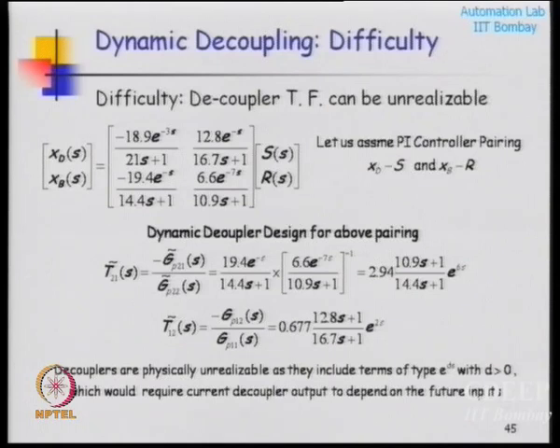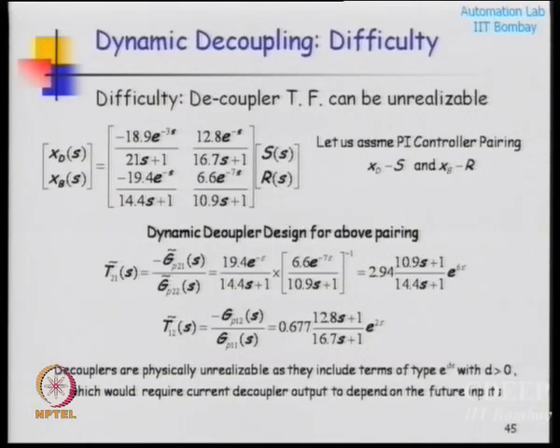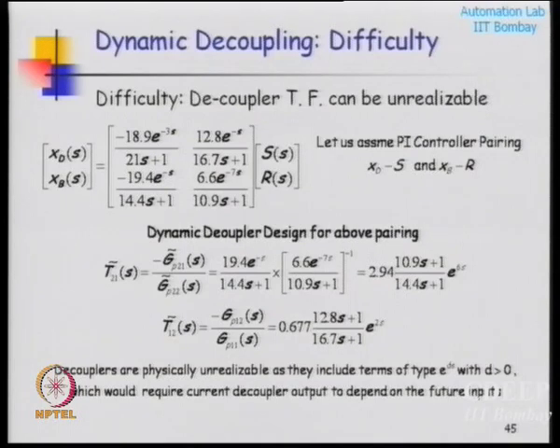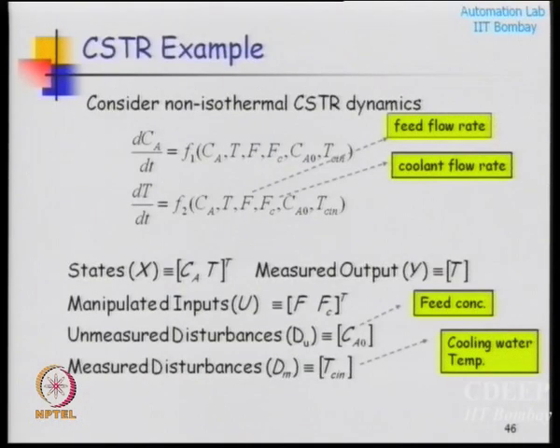Decoupling can be used for small systems - two-input two-output or maybe three-input three-output - but it has limited power because the model has to be perfect. The main advantage is that you do not need any special software; you can implement decoupling ideas through a normal DCS or PLC hardware off the shelf. But beyond small dimensional systems, this does not help us.